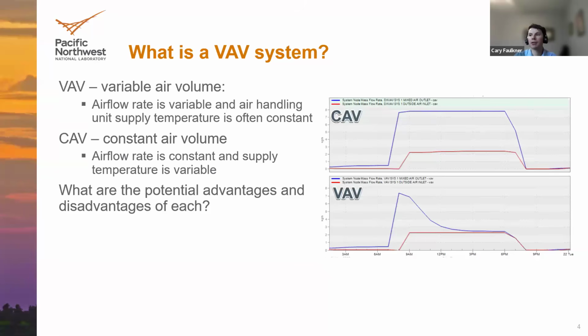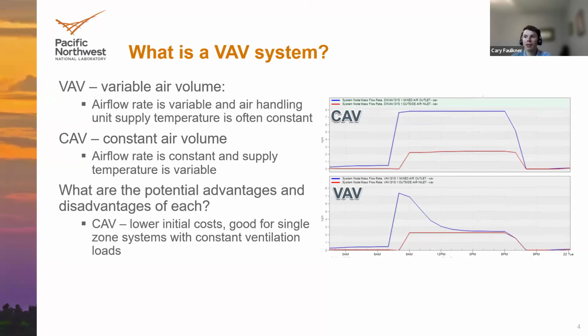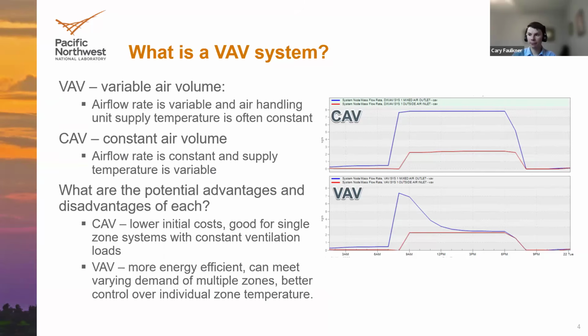So then what are the sort of trade-offs between these two different systems? Like why would you choose one over the other? Constant air volume systems might have lower initial costs. They're kind of simpler systems. They're good for single zone systems or maybe homes, or smaller buildings with more constant ventilation loads, and you can just kind of turn them on and off to meet the loads of that building.